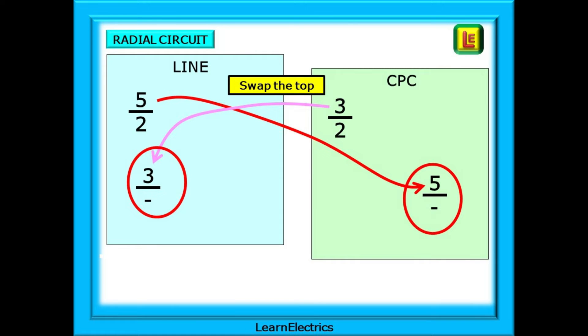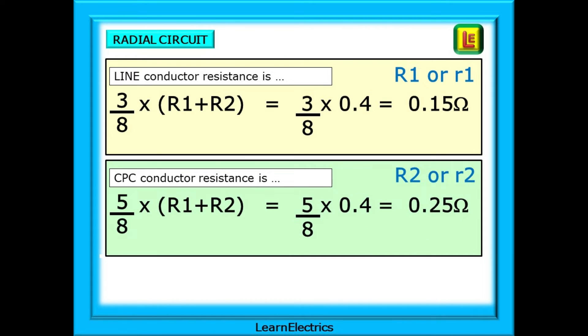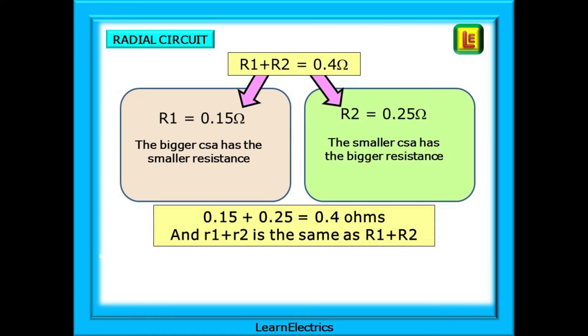Swap the tops: the 5 for the line goes onto the CPC side, and the 3 for the CPC crosses onto the line side. Now add the two top numbers — 3 plus 5 is 8. Then put 8 on the bottom of each fraction to give us 3 over 8 on the line side and 5 over 8 on the CPC side. These are called the multiplier fractions. We can now calculate the values of r1 and r2 as separate resistances. We already know the effective resistance is 0.4 ohms. For the line, 3 eighths of 0.4 is 0.15 ohms. For the CPC, 5 eighths of 0.4 is 0.25 ohms. Adding the two results together, we are back to 0.4 ohms, as we would expect.